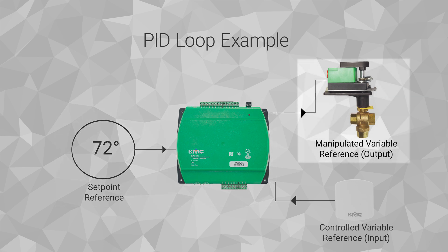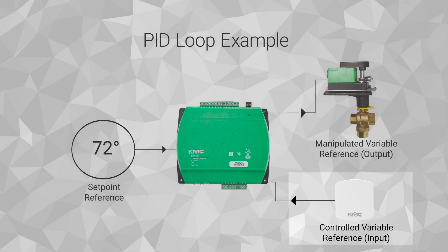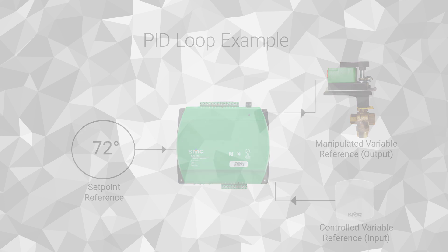The output of the control loop controls the valve through the BACnet loop object's manipulated variable reference property. The zone temperature sensor is represented to the loop with the BACnet loop object's controlled variable reference property and provides feedback to the loop. When the zone temperature does not match the set point, the loop commands the valve to open or close until the zone temperature matches the set point.